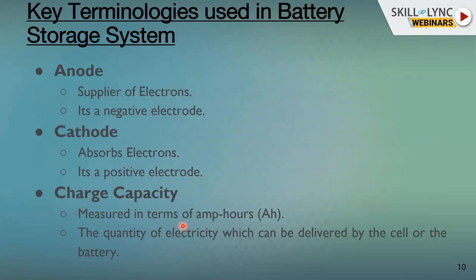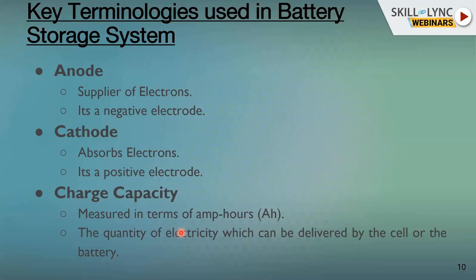Let's understand battery storage systems through some key terminologies. Anode is the negative electrode, rich in electrons — it supplies electrons. Cathode is the positive electrode, capable of absorbing electrons. Charge capacity is the quantity of electricity that can be delivered by the cell or battery, usually expressed in ampere hours (Ah). When you buy a battery, the capacity is expressed in Ah — meaning how much current the battery can provide and for what duration.